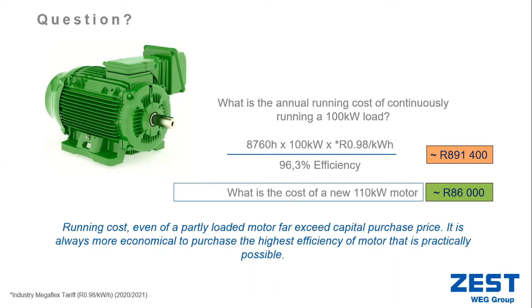It gets more shocking. What would be the cost of such a motor if I would go and purchase a 110 kilowatt motor currently? And that would equate to an amount of 86,000 Rand. So the running cost, even of a motor that's not fully loaded, far exceeds what we actually look at as the purchasing price of the motor. And that's why it's always the best advice, when purchasing a motor, to look at the highest efficiencies available.